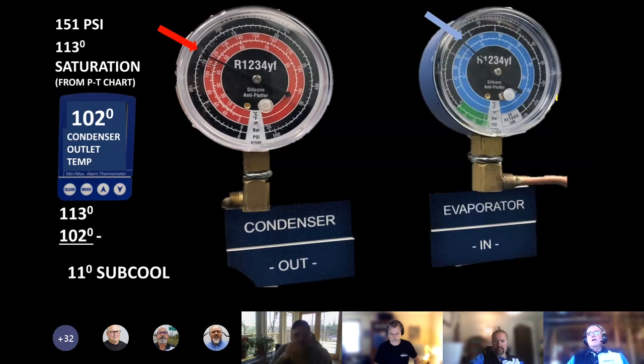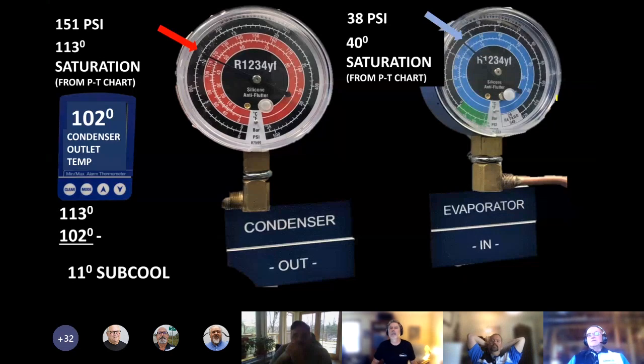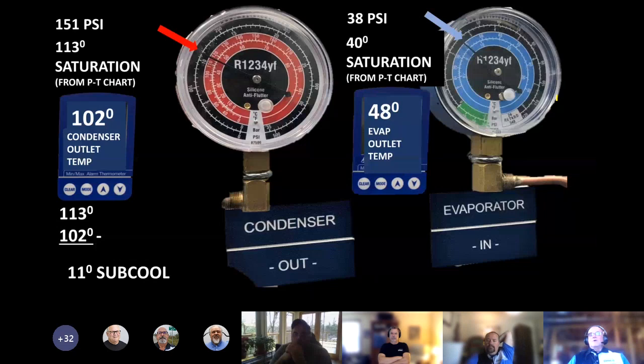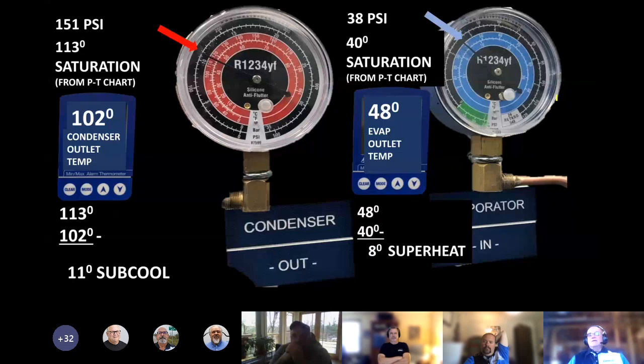If we go to the low side, right now we're getting a pressure of 38 psi on the low side. Using the chart, we get 40 degrees of saturation temperature. Now we measure the outlet temperature of the evaporator with our thermometer, and we get 48 degrees. And using the math, we got 8 degrees of superheat, which is again a good reading for this system.